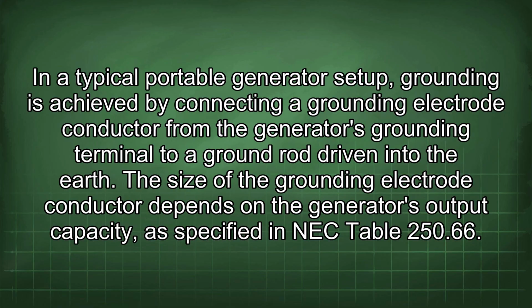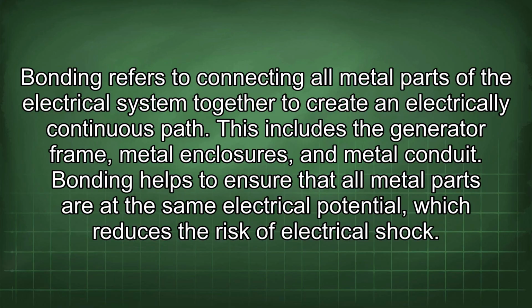In a typical portable generator setup, grounding is achieved by connecting a grounding electrode conductor from the generator's grounding terminal to a ground rod driven into the earth. The size of the grounding electrode conductor depends on the generator's output capacity, as specified in NEC Table 250.66. Bonding refers to connecting all metal parts of the electrical system together to create an electrically continuous path.